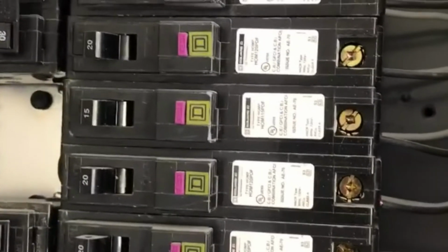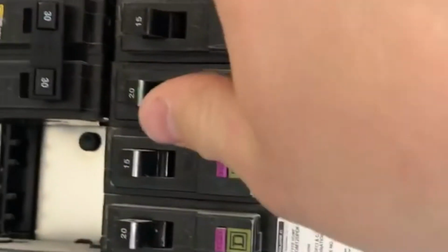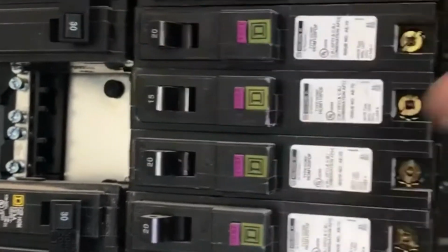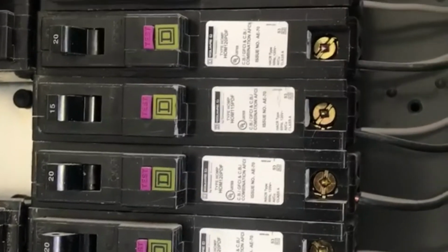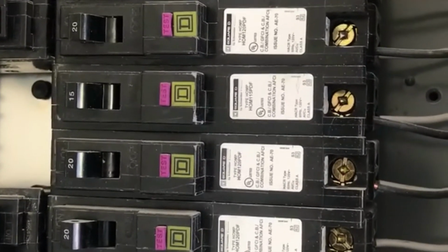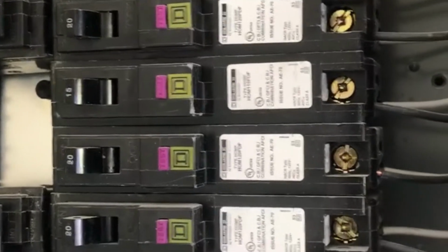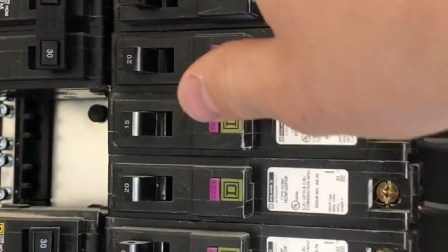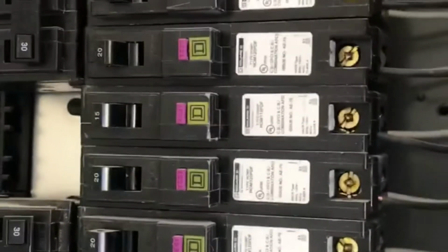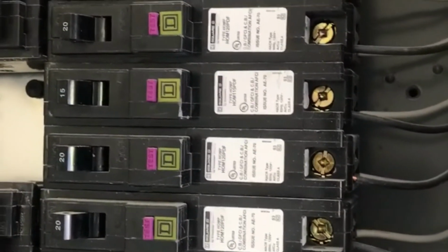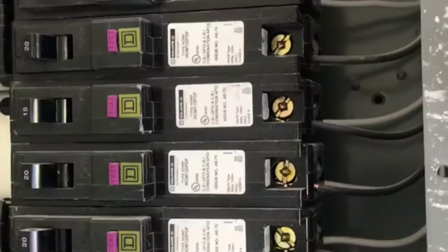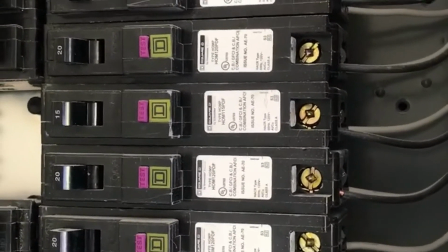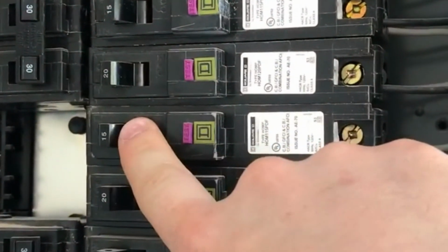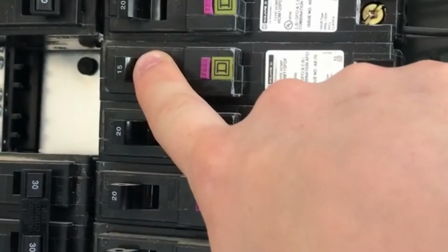As you can see with the 110 or 120 breakers, there's 20 amp and 15 amps. 15 amps are used whenever there is a 14 gauge wire utilized in a circuit. Generally, houses use 14 and 12 gauge wire for 120 volt purposes. As 14 is a smaller gauge wire, it can only hold the 15 amps of current to eliminate any potential issues with overpowering the small gauge wire.